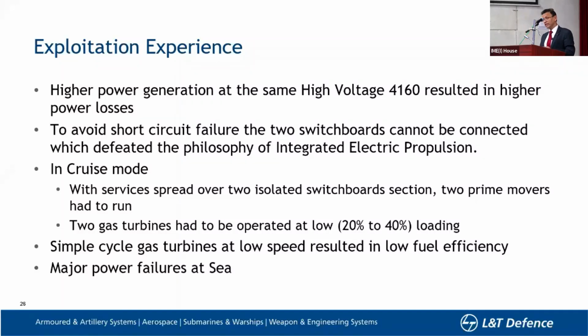To avoid short circuit failure - normally on an integrated electric propulsion system, it's an island where all the generators feed a common bus bar - but in the US DDG, they decided not to couple the two switchboards. There was a separation between port and starboard power supply, which, if you think about it, is not truly integrated electric propulsion. But to prevent short circuits, they went for this concept.